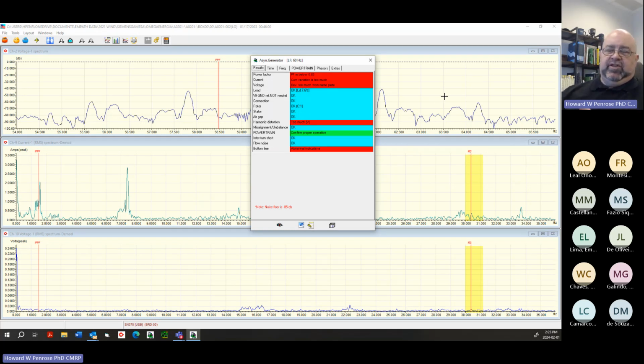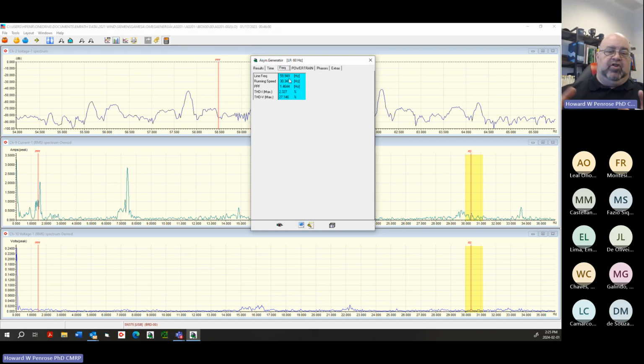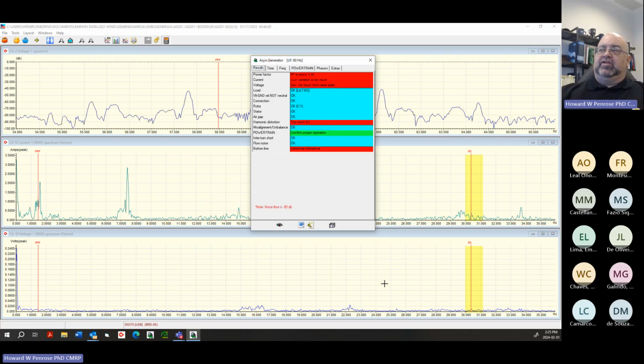And that's how it's generating a constant 60 hertz. A little different when dealing with an induction generator, because that goes through an inverter. But on our DFIG, everybody's design ends up at a constant speed. If it goes a little faster, it changes the output frequency; if it goes slower, it changes the output frequency. You can actually look at the frequency it selects to determine where you're going to be roughly. But when I go through a site, somebody set up all of these things and it just so happens to be about 1820 RPM - they basically cut and paste the programming from tower to tower, so they're all going to be 1820 RPM. The other nice thing is matching up that peak to a pole pass frequency. A pole pass frequency will not relate to anything else and will show up in both current and voltage.